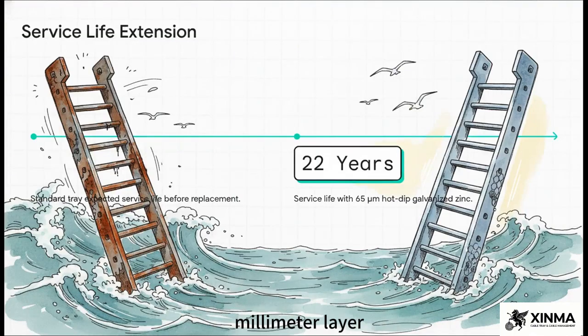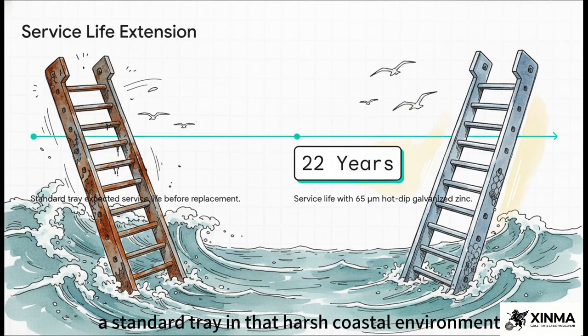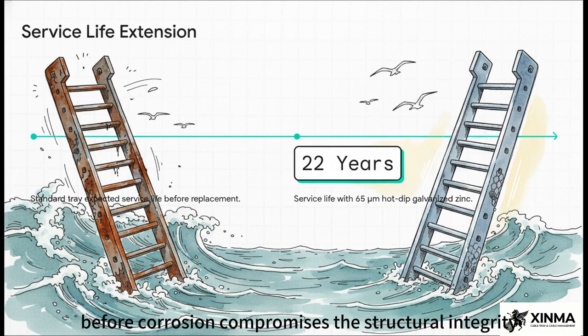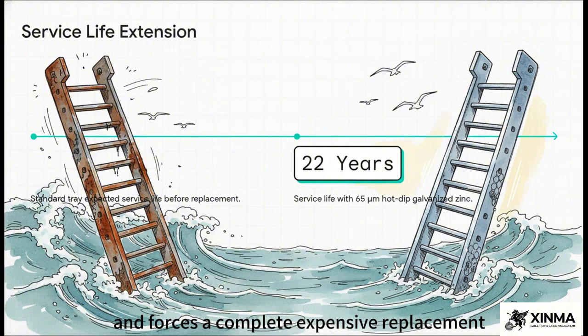That 65 micrometer layer builds a completely different life cycle. A standard tray in that harsh coastal environment has an expected service life of a mere 7 years before corrosion compromises the structural integrity and forces a complete expensive replacement. But by specifying that one robust layer of hot-dip galvanized zinc, the installation's service life was extended to an impressive 22 years.